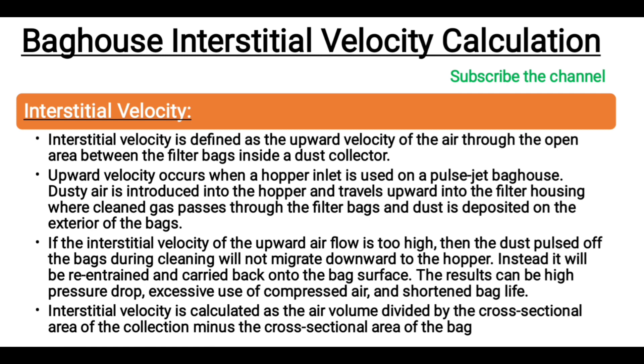What will happen if interstitial velocity is too high? If the interstitial velocity of the upward airflow is too high, then the dust pulsed off the bags during cleaning will not migrate downward to the hopper. Instead, it will be re-entrained and carried back onto the bag surface. The results can be high pressure drop, excessive use of compressed air, and shortened bag life.